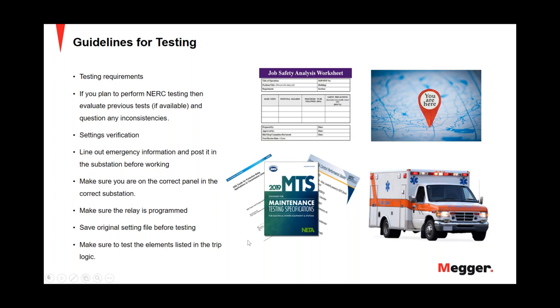Make sure the relay is programmed and that you have the original setting file before you test. When you go to the relay, you want to pull the original file out before doing any testing — save it as an 'as-found' file in its own proprietary format. So if we're doing the SEL 351, use the appropriate software — Accelerator — save the original file, and then start adjusting things. If something happens during the test, you have the original file to dump back into the relay and not leave it unprotected.